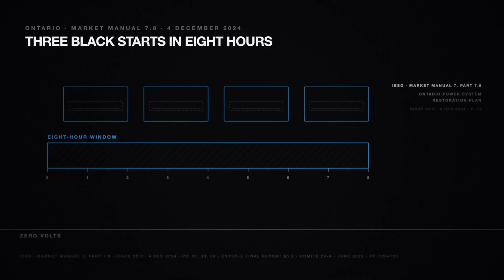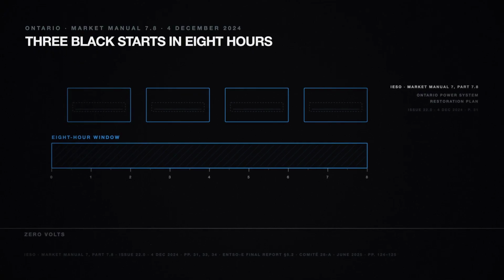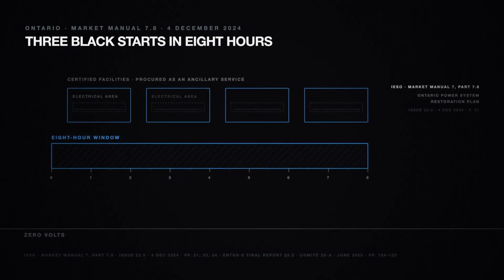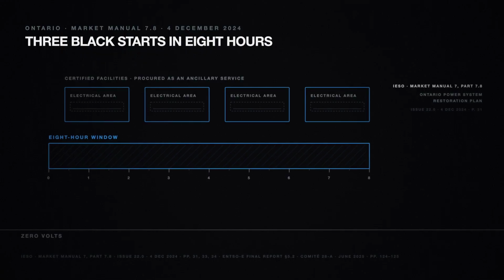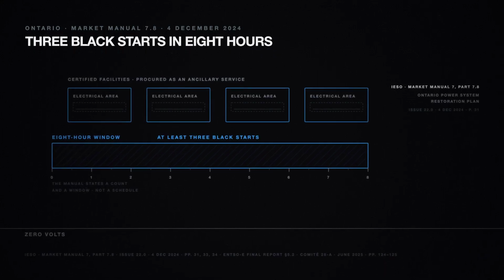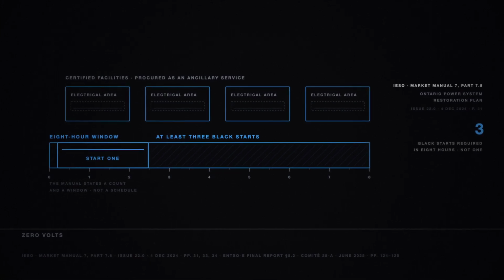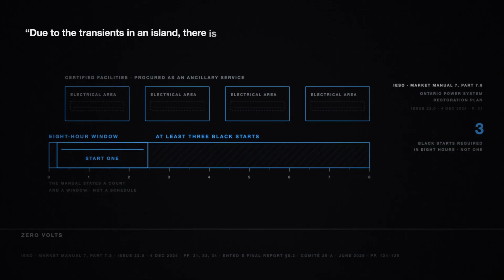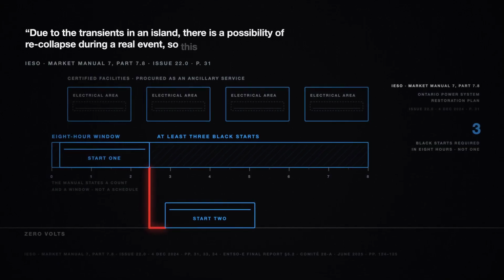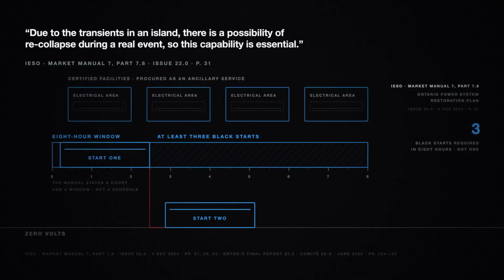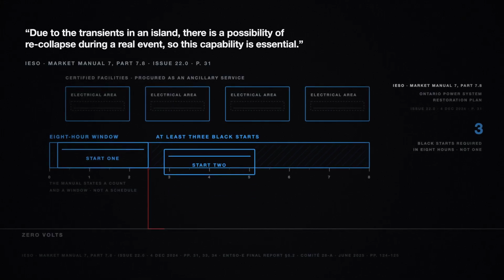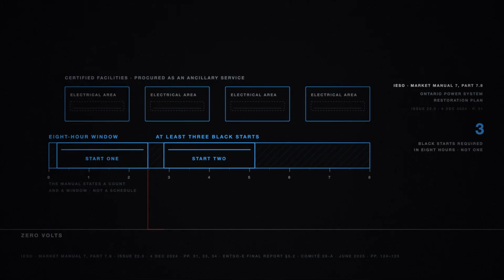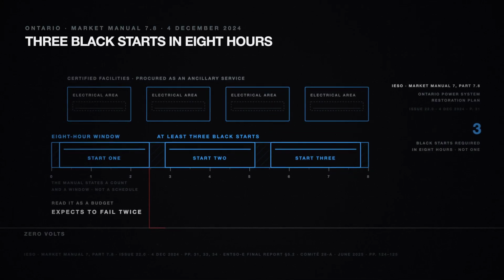Ontario publishes what a tested Black Start capability looks like. Market Manual 7, Part 7.8, December 2024. Certified facilities are procured as an ancillary service, ideally one in each of 4 electrical areas. And each certified unit must complete at least 3 Black Starts in 8 hours. 3, not 1. The manual gives its own reason. "Due to the transients in an island, there is a possibility of recollapse during a real event, so this capability is essential." Read that as a budget. It assumes the first attempt may not hold and the second may not either. The plan for the worst day expects to fail twice.